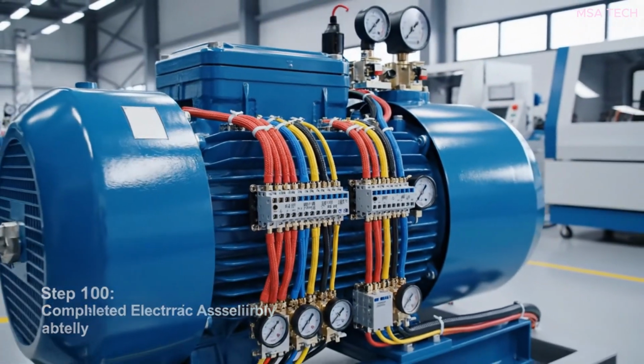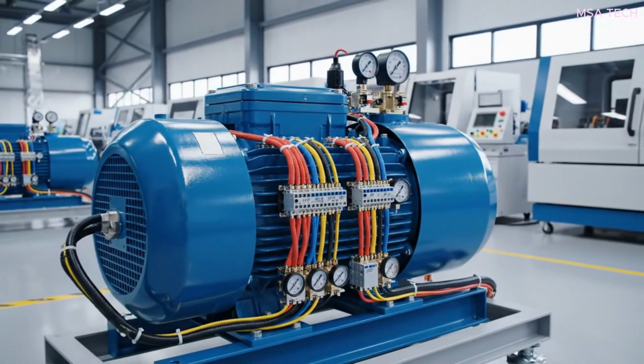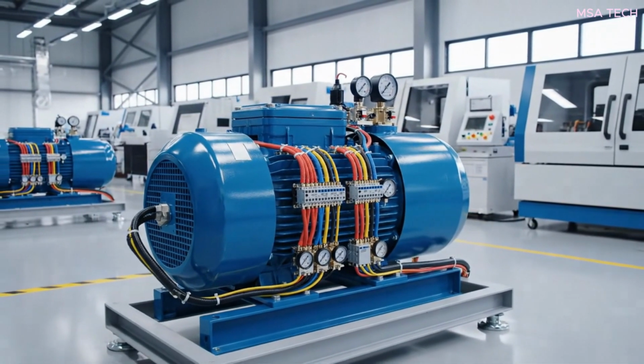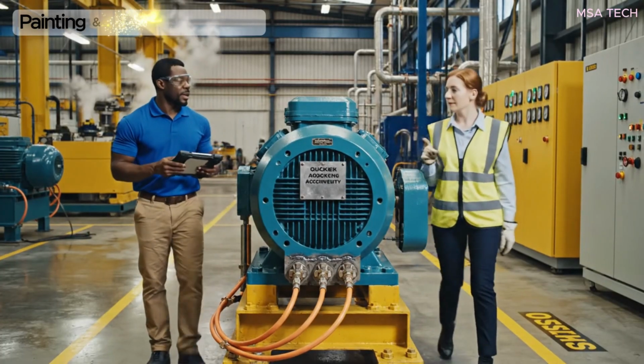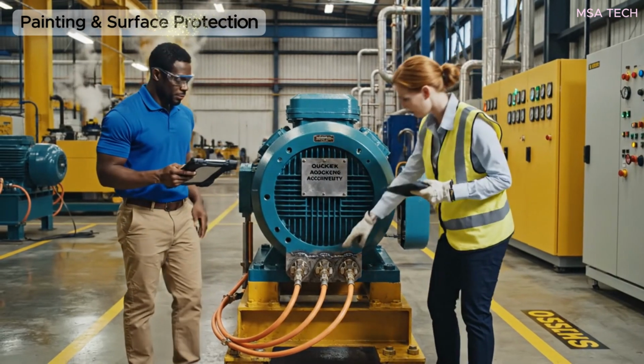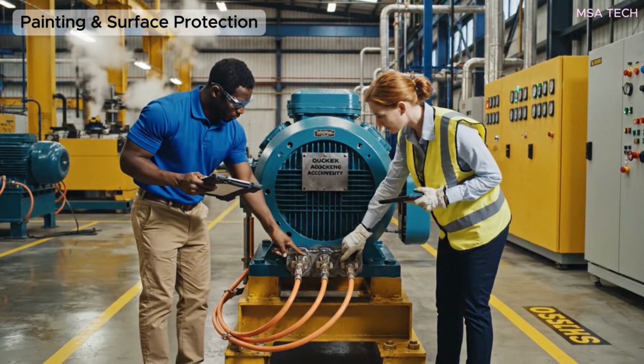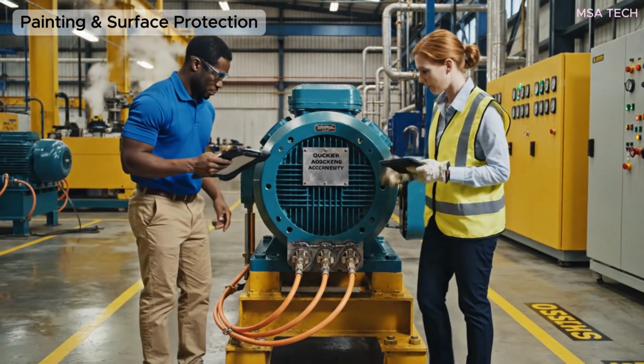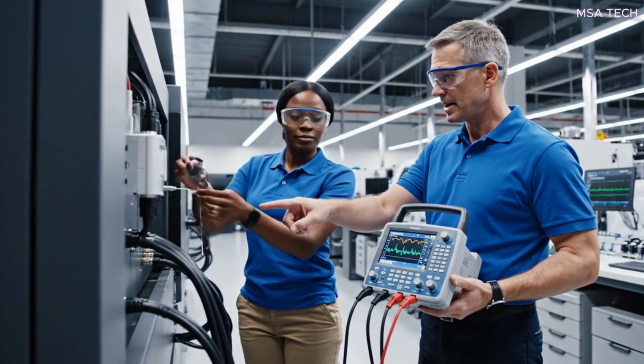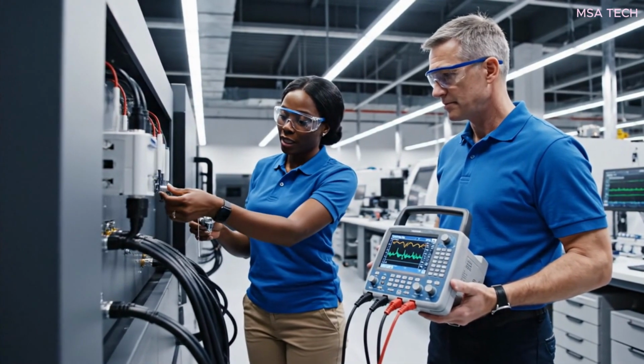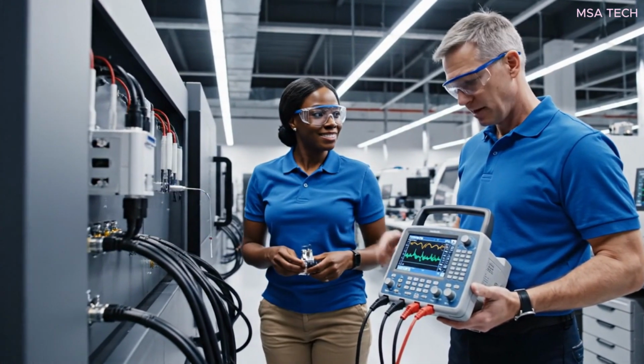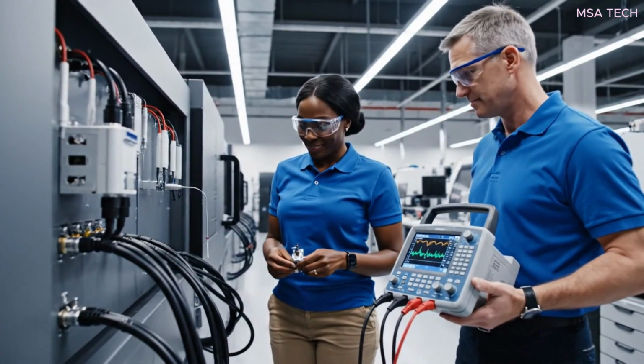Step 100, the completed electrical assembly. This motor is now ready for comprehensive testing and final commissioning. Cross-referencing the nameplate now, everything aligns. Good. I'm checking the fasteners on the base. All secure. We need to verify the signal integrity on the analyzer. The probes are connected and secure. Verified. Looks stable. Let's start the sequence.